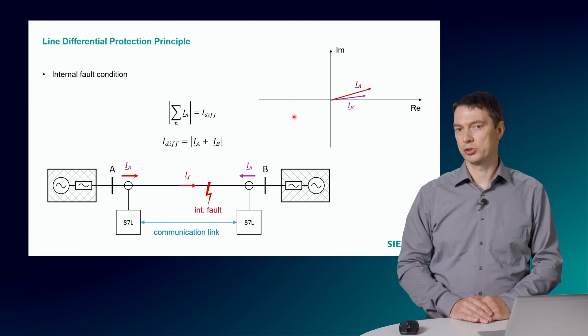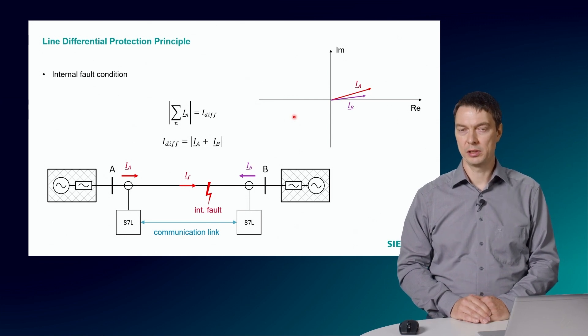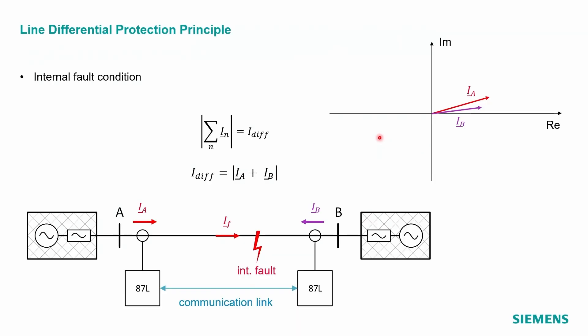For the internal fault condition, the phasor measured at the terminals A and B appear in the same direction on the complex plane. The sum of both phasors will result in a very big differential current. Here we also consider some CT errors, which are expressed by the circles at the top of these phasors. For the internal fault condition, these errors are not so important as the differential current amplitude is very high and the relay will typically operate and trip the circuit breaker.